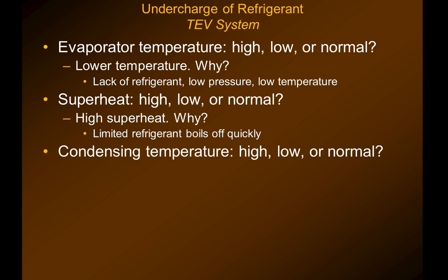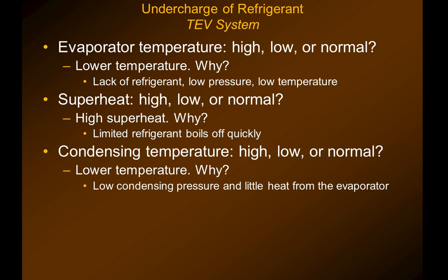Is the condensing temperature going to be high, low, or normal? It's going to be lower, just like the evaporator temperature, for the same reason — because of the low pressure. There's not a lot of refrigerant, and with a limited amount of refrigerant, it doesn't absorb as much heat out of the box as it can. When it doesn't absorb heat, the temperature lowers.